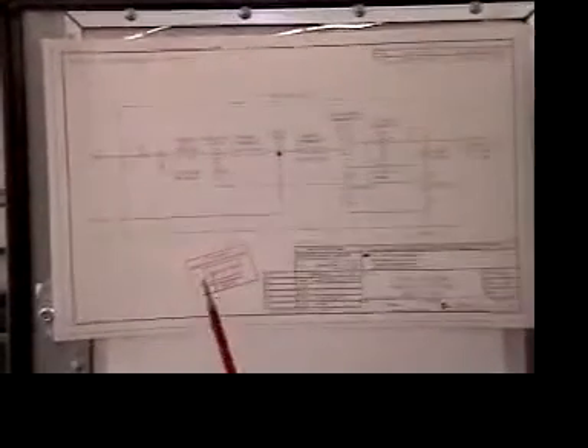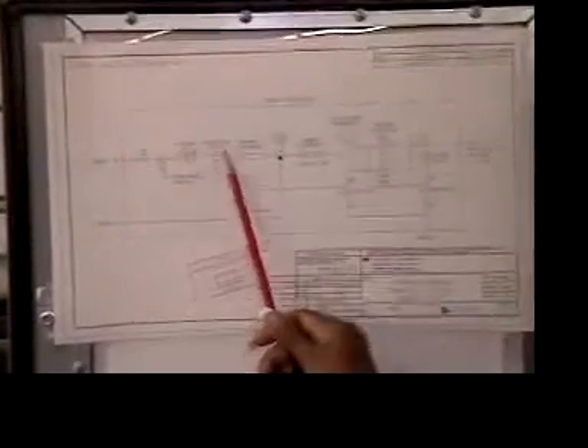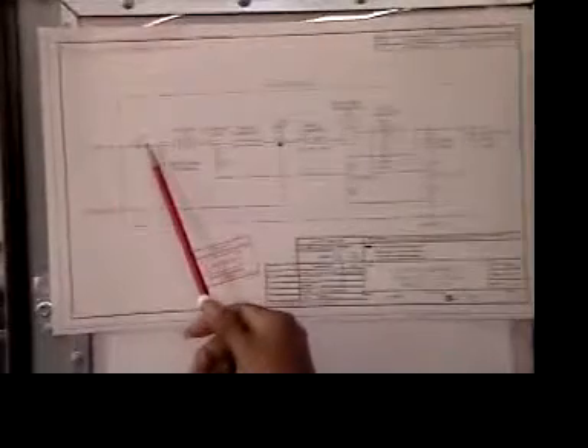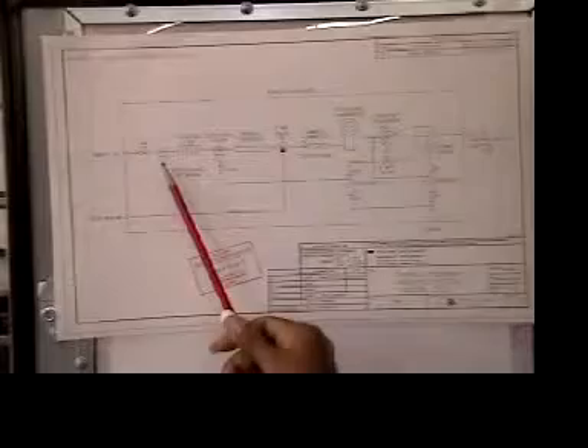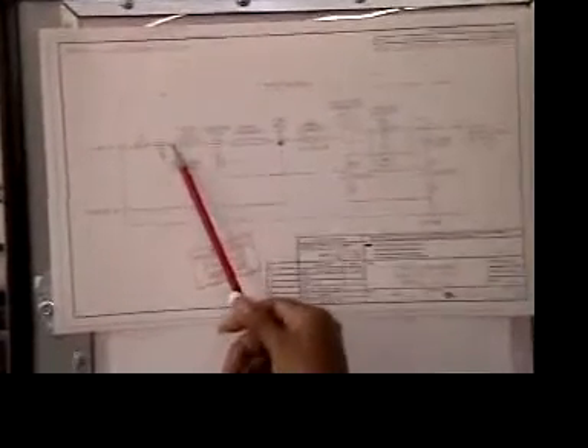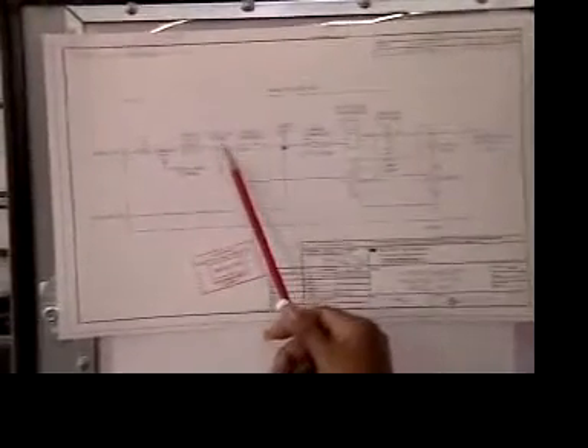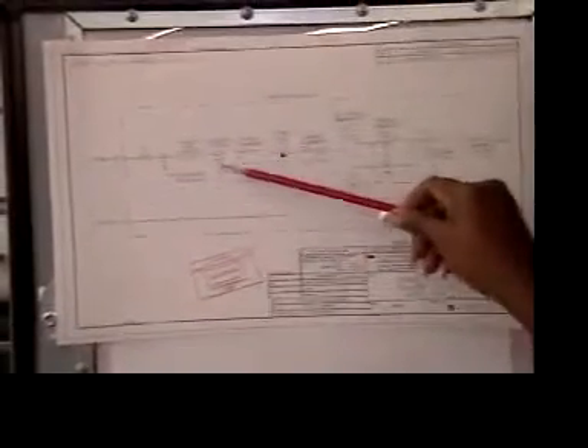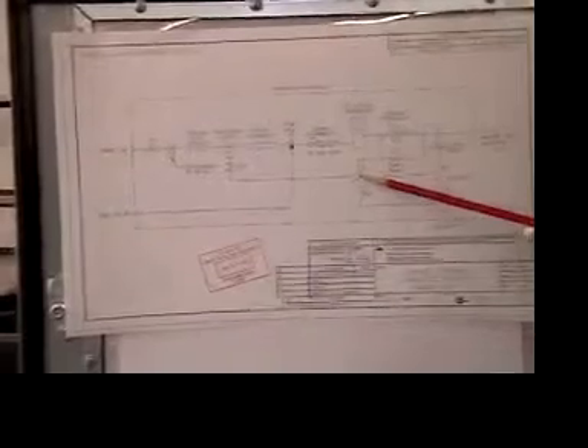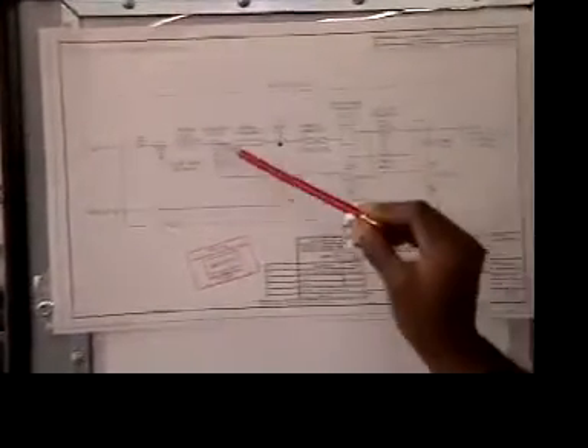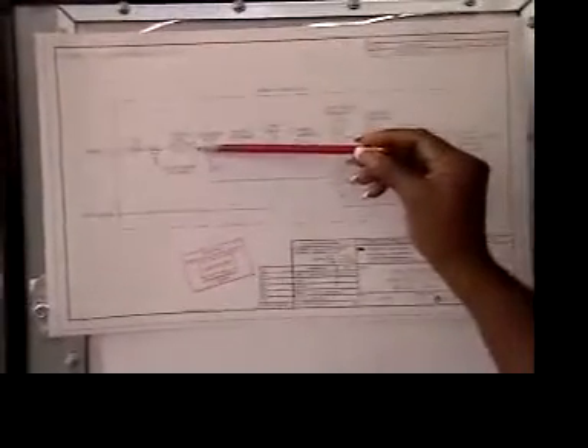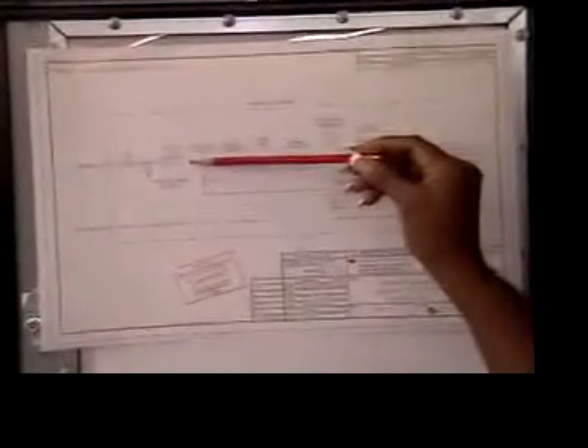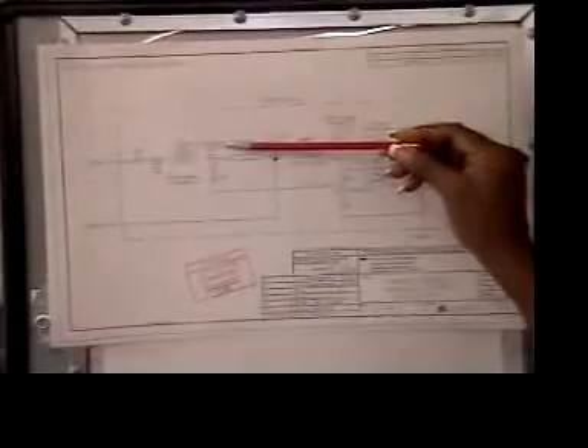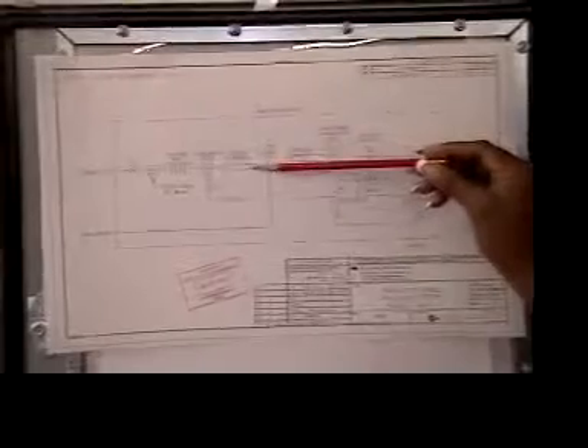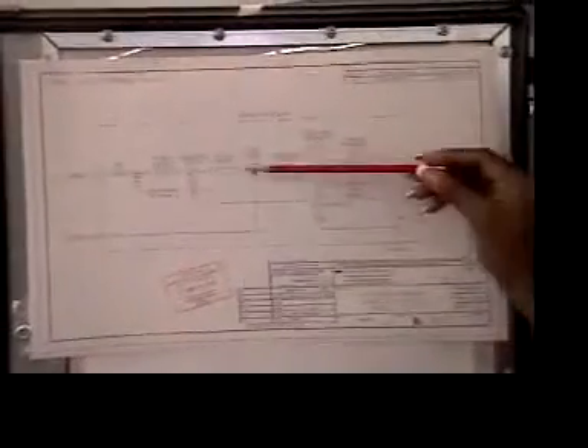Let's look at the piping diagram, the flow diagram, so we can see how the sample travels through the sample handling system, through the analyzer and back out to the exhaust. The sample comes in through valve V4, through a guard filter, a 90 micron filter, then through a cooling coil to a coalescent filter. The coalescent filter drains through V5 and goes to the yellow input of the eductor E2. Just the water, the condensate, drains, but the sample continues to travel through our Purafil scrubber, where the acid gases are scrubbed out so that the clean sample can get to the analyzer.